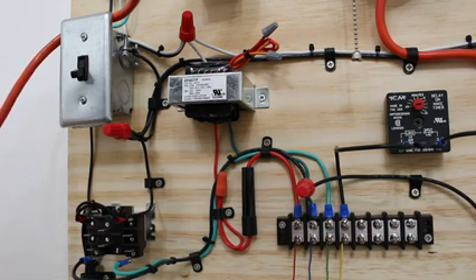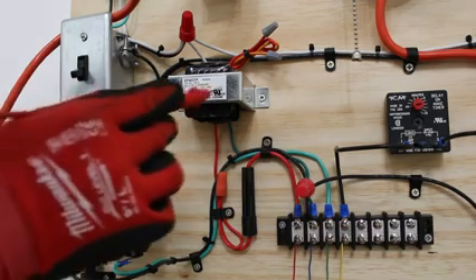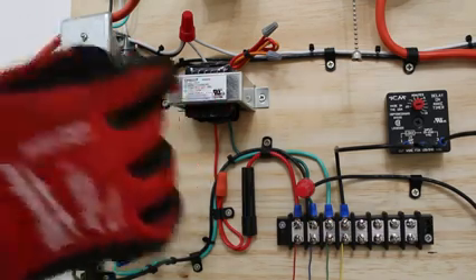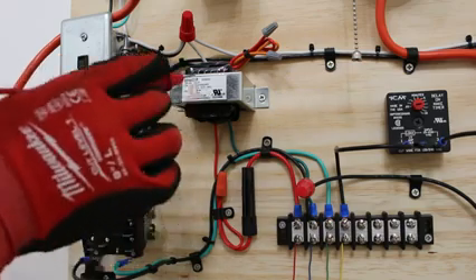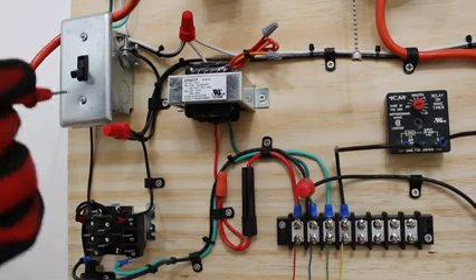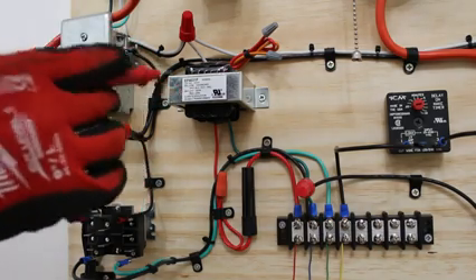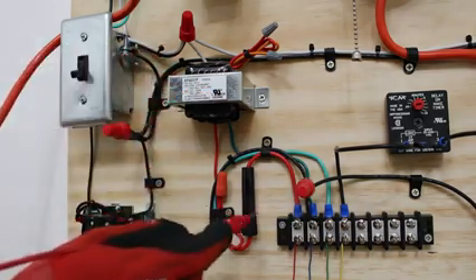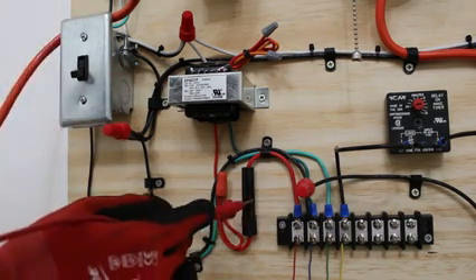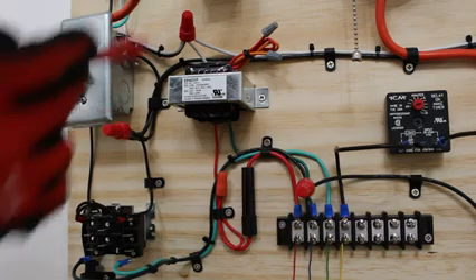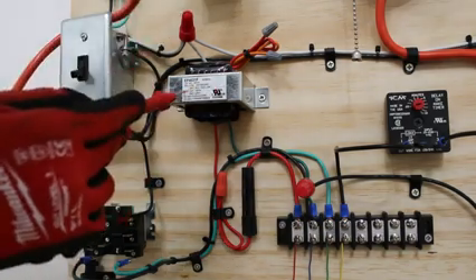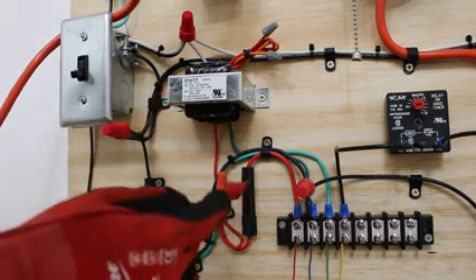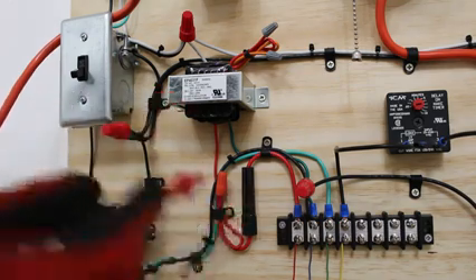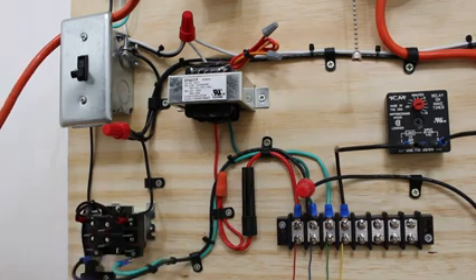But before you can make that decision, make sure that there's no reset button or little breaker, any type of switch that you see on the transformer, because if that trips, you wouldn't have a secondary voltage. A lot of times they do have this protection. In this case, we do not have one, but if you follow the wiring, we do have an inline fuse. So you would turn off the power and make sure that your fuse is actually not blown. So if you have your incoming power, you don't have a switch here that tripped, and in this case we have a fuse and the fuse is good and you still don't have 24 volts, your transformer is bad.